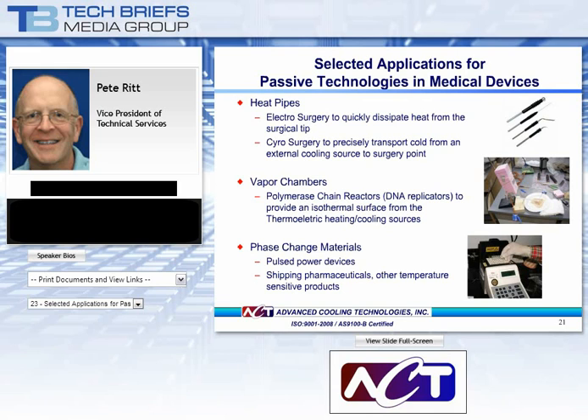Let's look at some selected applications for these passive technologies in medical devices. Heat pipes can be used in forceps for electrosurgery applications to quickly dissipate heat from the tip. This enables the surgeon to move quicker and safer during the procedure, reducing the risk of burning unintended tissue. Titanium heat pipes are generally used here. Heat pipes transport cold as well as heat and can be used for cryosurgery to precisely transport cold from an external cooling source to the surgery point.